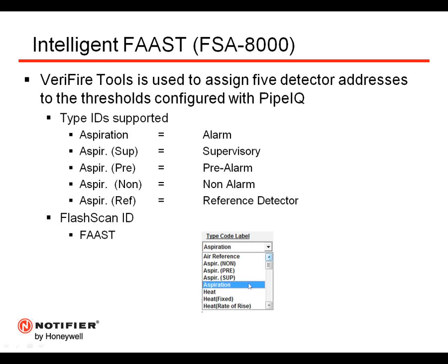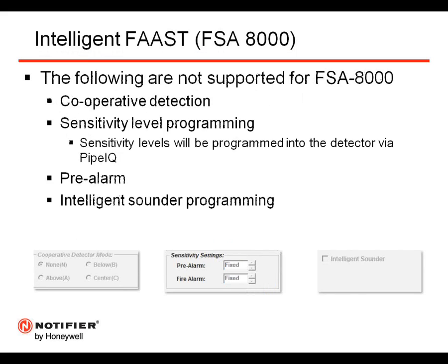And here is a screenshot from VeriFire Tools. So now with VeriFire Tools version 7.00 or higher, these are the aspiration type codes that are available for intelligent FAAST. The following are not supported, so it can't participate in cooperative detection. The sensitivity level programming is grayed out because, as we discussed a couple of slides earlier, the sensitivity levels are going to be programmed in the detector via the system sensor Pipe IQ utility. And also, we don't have intelligent sounder programming because it's not a spot detector that could potentially sit in a B200S addressable sounder base.